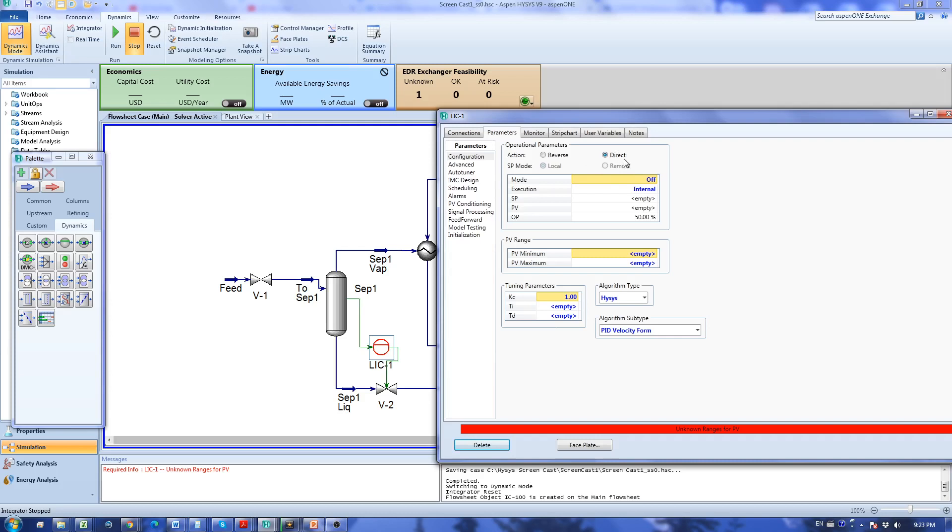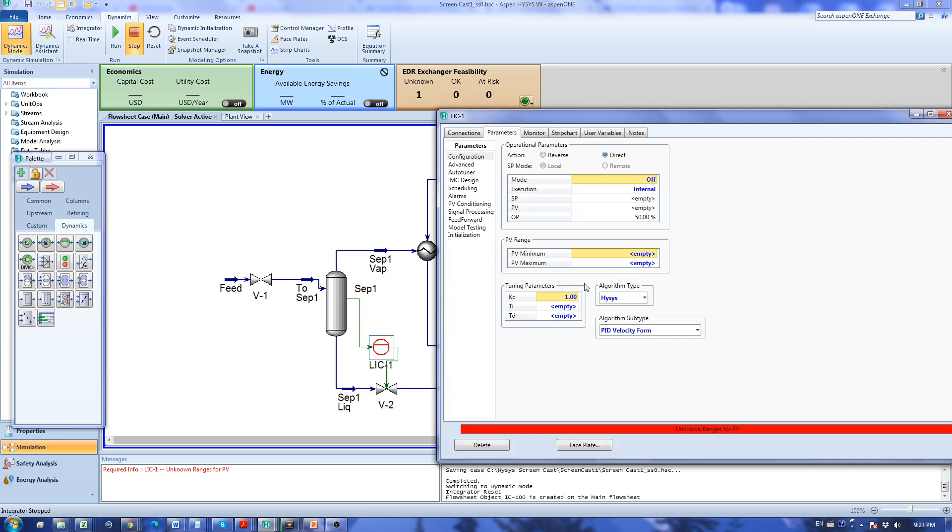I'm going to start off in manual mode before going to automatic. It didn't go through because I have to first specify some other values. For the PV range I'm going to specify from 0 to 100 percent of liquid level and now it accepts the manual mode.